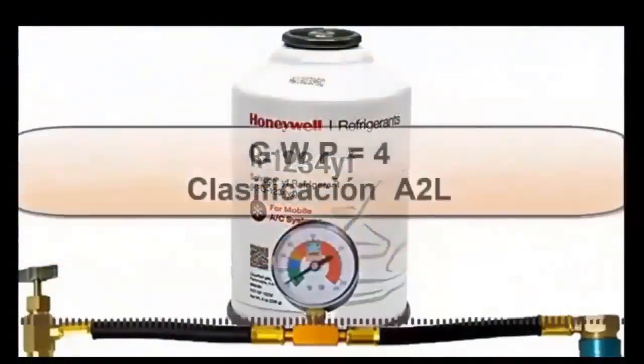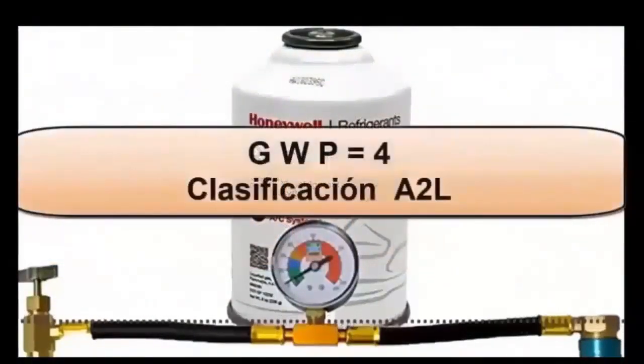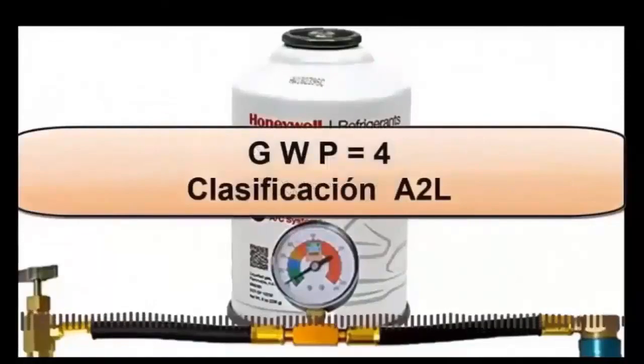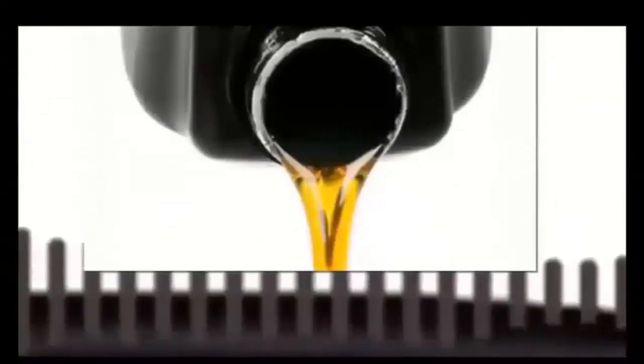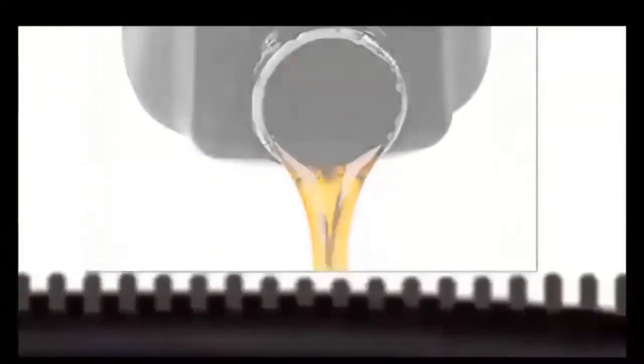The safety classification of R1234YF refrigerant is A2L. R1234YF refrigerant is miscible with POE polyol ester synthetic oils and PAG polyalkylene glycols, so it should always be used with this type of oil.